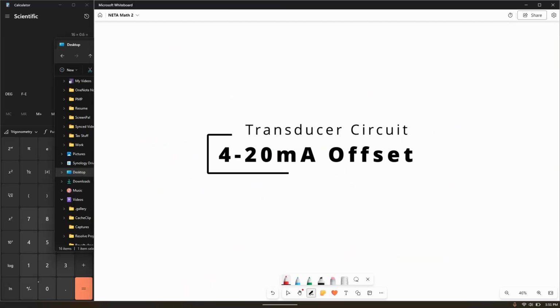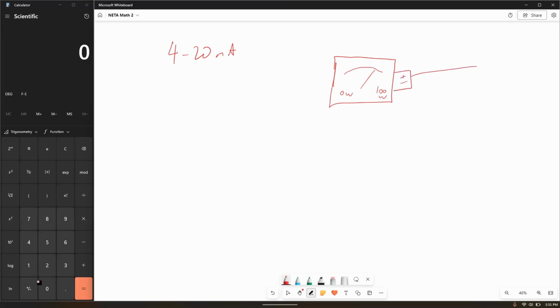Okay, last but not least, I want to make an honorable mention of something that I remember from one of my tests, and it's not that hard, but it definitely can throw you off. So if you're not familiar with a 4 to 20 milliamp transducer, essentially what it is, say I've got a power meter. Over here on this end of the scale is 0 watts, and say over here is 100 watts. So I can visually see what percentage of the full scale we're currently at right now. And then I'm going to have a transducer attached to that. Going to have a loop circuit that's going to go to something else, say a remote display. We're going to call it a display. It could be anything else. It could be a PLC. It could be a relay. It could be another meter. It could be some other process equipment that's dependent on this meter reading.